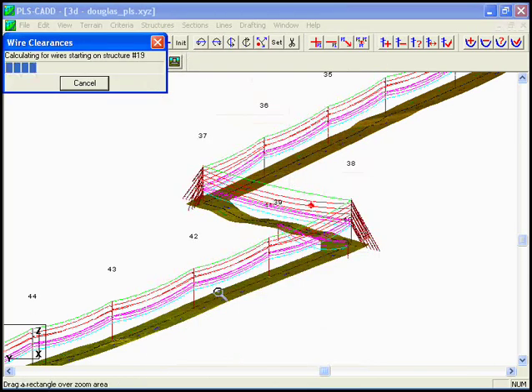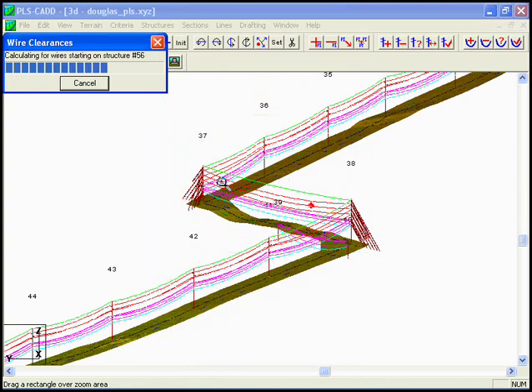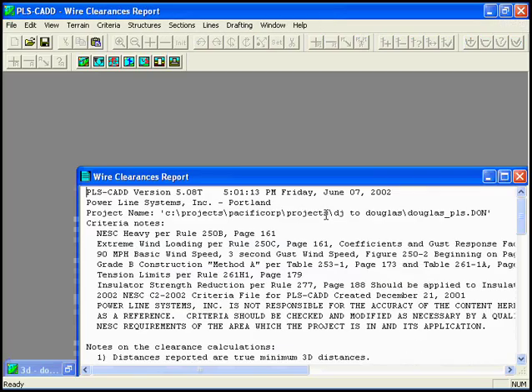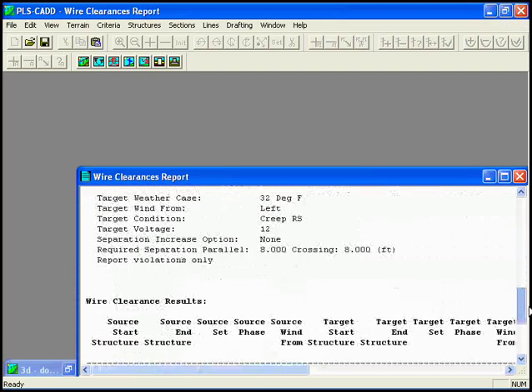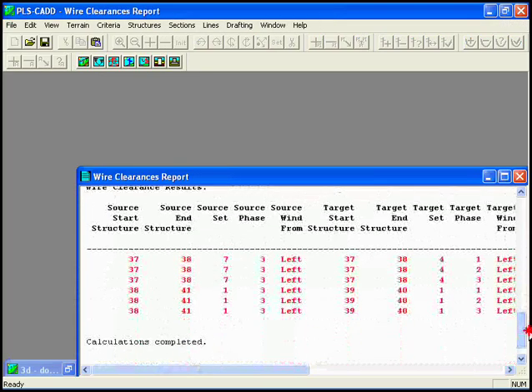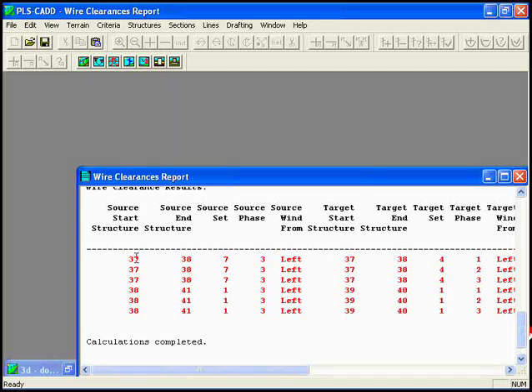Click OK, and in about a second per mile we will have an entire clearance check of all the phases, and we can slide down this and see that we do have some clearance problems, and they all occur between 37 and 41 structure numbers, as we figured.